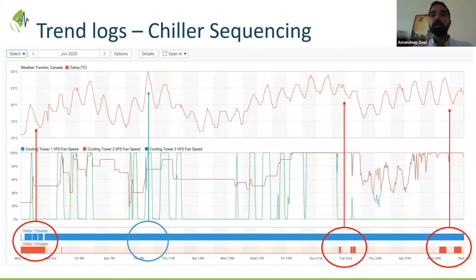And in fact, all of the times when you have the 2 chillers come on at this time, you did not need those 2 chillers to come on, because when you look at the blue circle, that's when it was 30 degrees outside and 1 chiller was able to maintain the set point in the building. But all the other times, even though the outside air temperature was lower, still the 2 chillers were coming on. You could only figure this out if you have a good set of trend logs to optimize the chiller system. And in this case, all Rob needs to do is basically review their programming language to make sure that the second chiller doesn't come on when it's not needed.